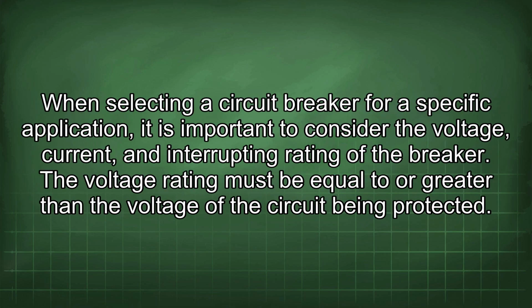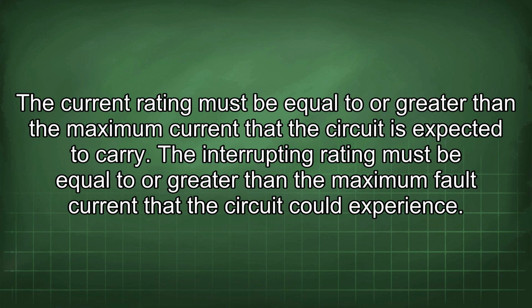When selecting a circuit breaker for a specific application, it is important to consider the voltage, current, and interrupting rating of the breaker. The voltage rating must be equal to or greater than the voltage of the circuit being protected. The current rating must be equal to or greater than the maximum current that the circuit is expected to carry. The interrupting rating must be equal to or greater than the maximum fault current that the circuit could experience.